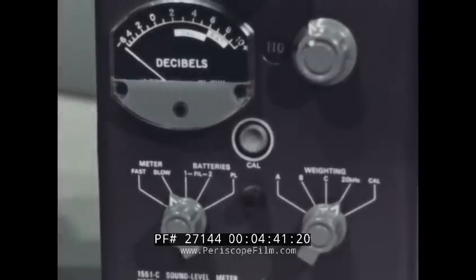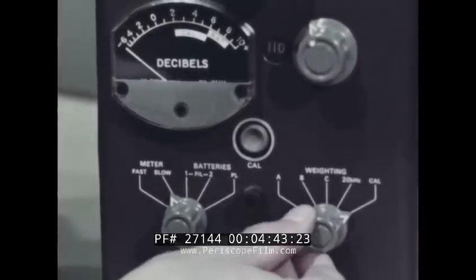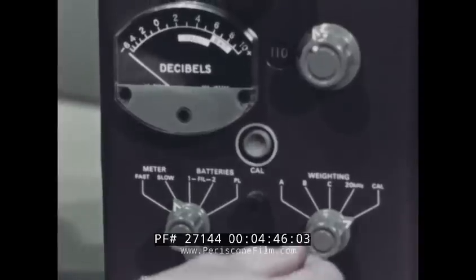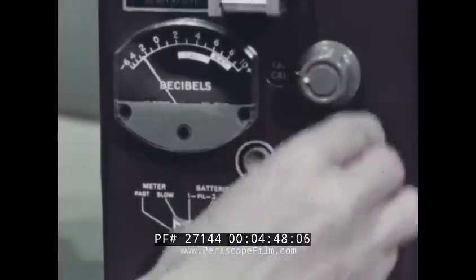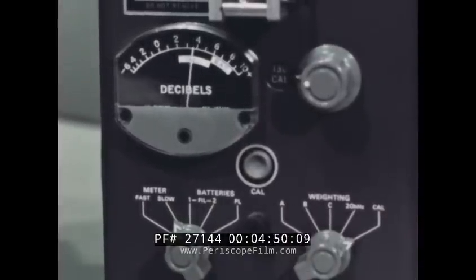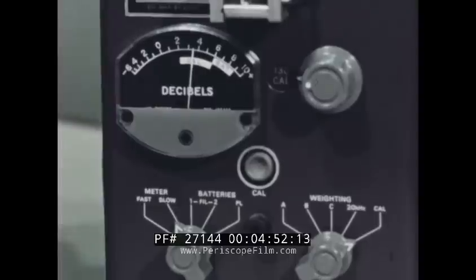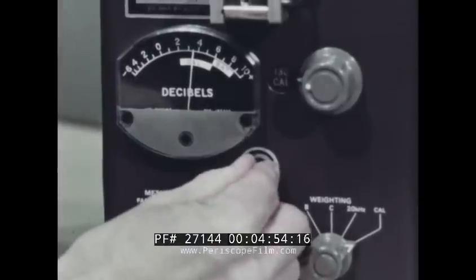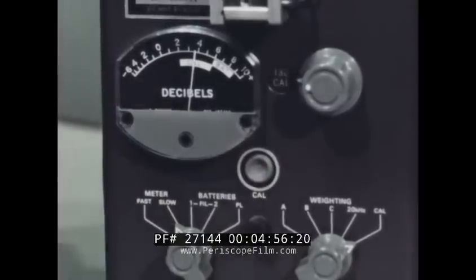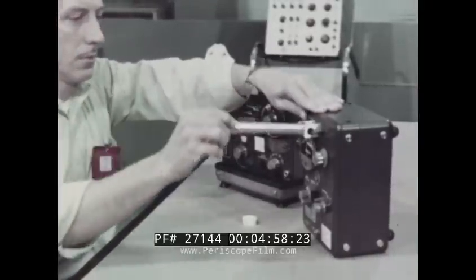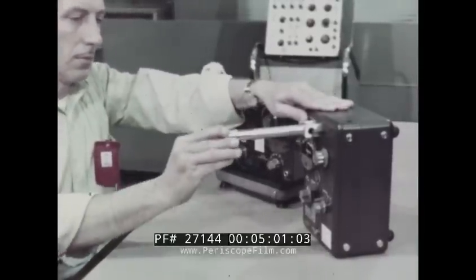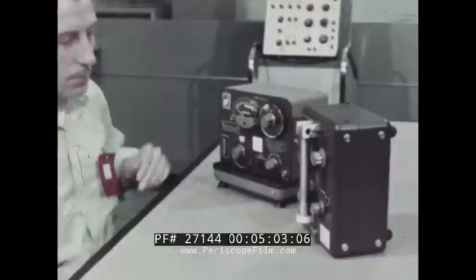Now set up for calibrating. Put the weighting switch to cal and do the same with the attenuator switch. The meter should now read in the cal area. If it doesn't, adjust the thumbset control. So much for the internal calibration. The next procedure checks on the accuracy of the meter readings.